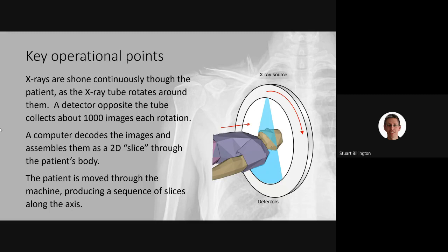It's almost as if the three-dimensional cone of a regular X-ray, which produces a two-dimensional flat image, has been squashed in one direction, so that effectively it's almost a one-dimensional beam of X-rays. It's going to take a picture of the width of the patient, but only a millimeter or so wide. The thickest it would ever be is about 5 millimeters, and quite often it's sub-millimeter in thickness.